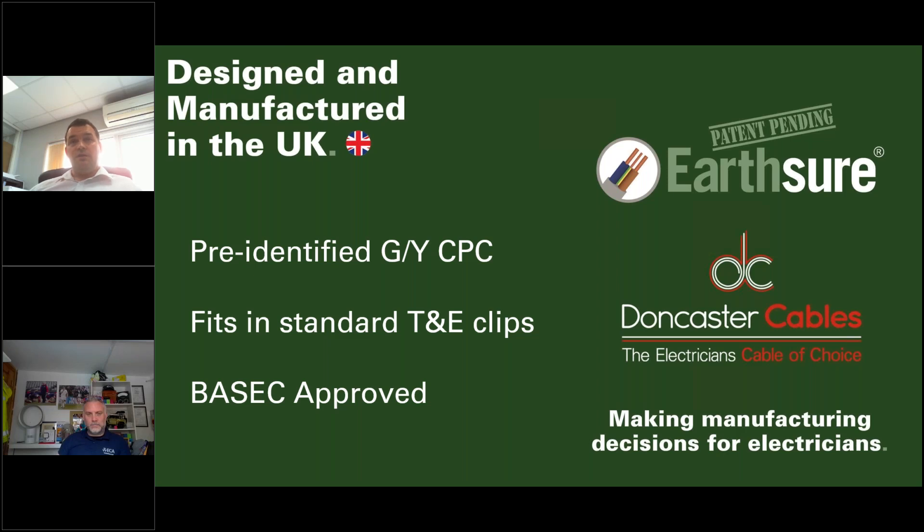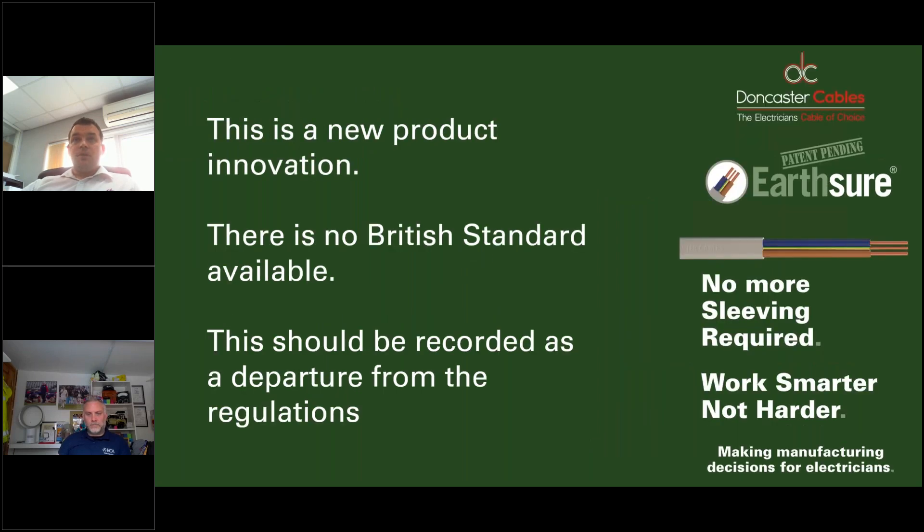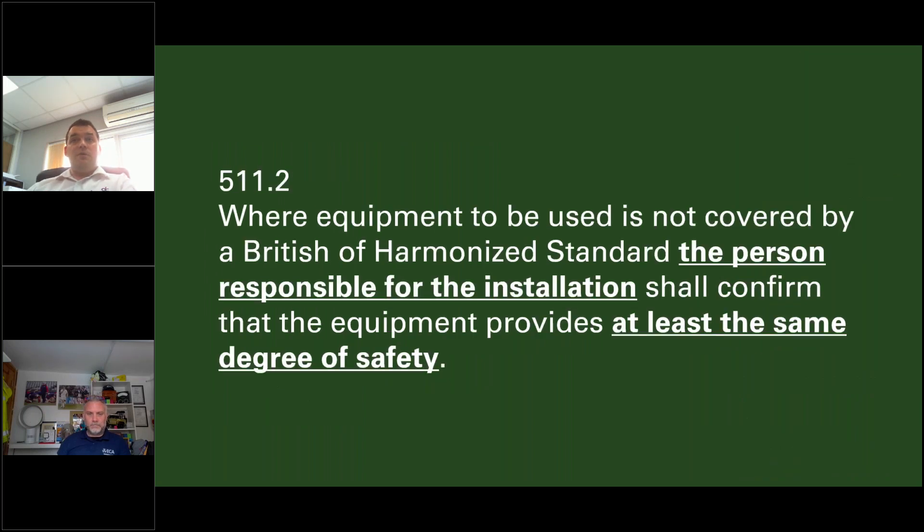Earthsure comes with a pre-identified green and yellow CPC and fits standard twin-and-earth clips — the sheathing is actually slightly smaller than normal twin and earth. We re-engineered and developed a special compound for the Earthsure sheathing which enhances the mechanical and electrical properties while still complying with all BS requirements that normal twin and earth meets. We obtained BASEC approval with a CAD encompassing all those enhancements. As with EVUltra, because it's a new product innovation with no British standard, using Earthsure should be recorded as a departure from the regulations, with the installer responsible for confirming it provides at least the same degree of safety.